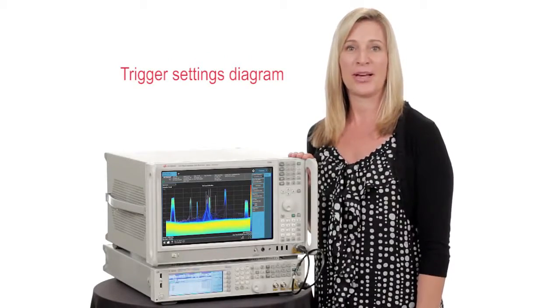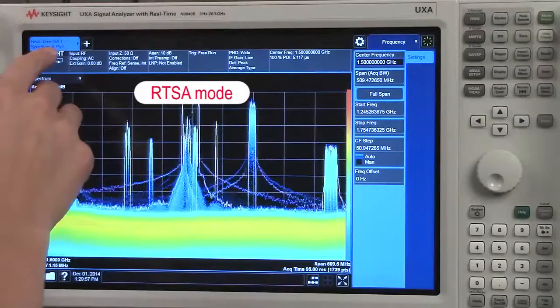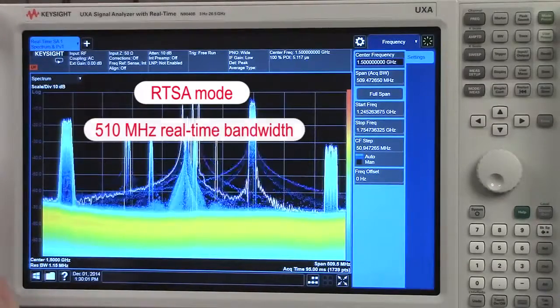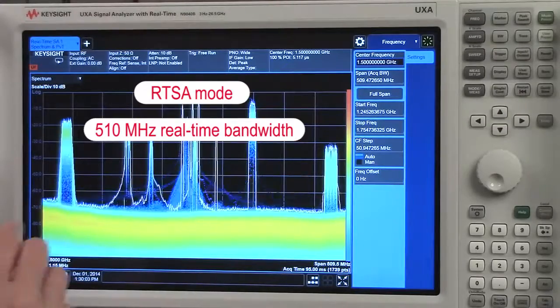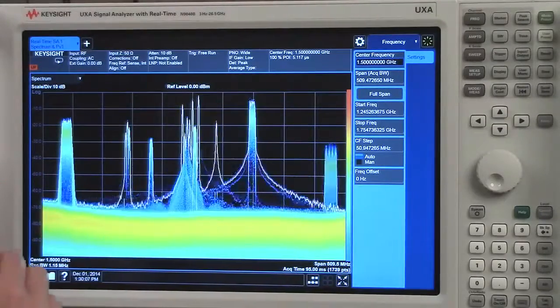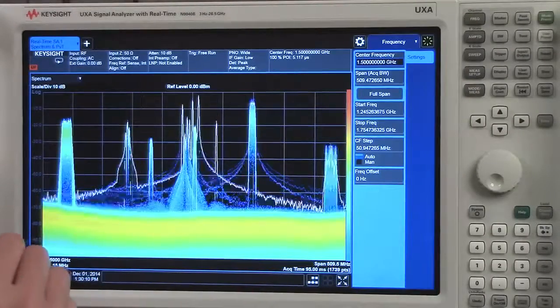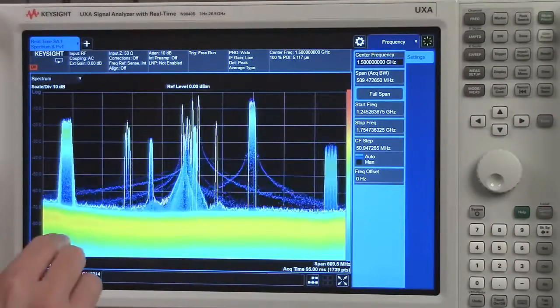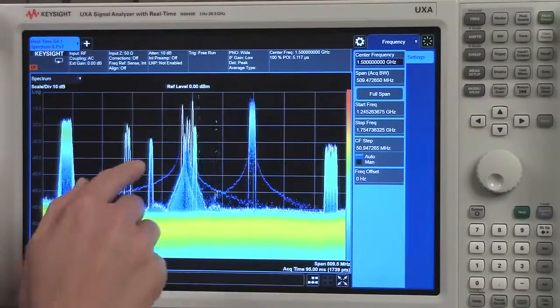So let me show you how to use this. We're in our real-time spectrum analyzer mode. We're spanning a full 510 megahertz of real-time bandwidth. We have various wireless communication signals and pulses going on in the spectrum. What I'd like to do is use our frequency mask trigger feature to trigger on this wideband CDMA signal.